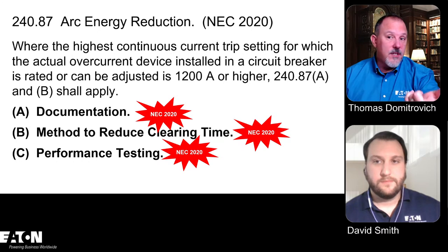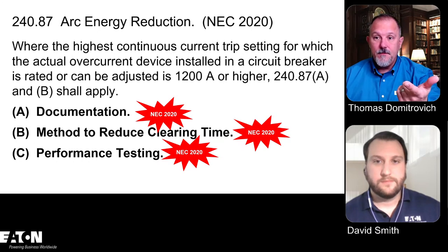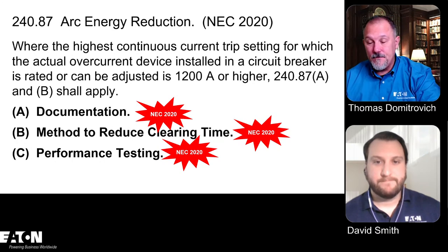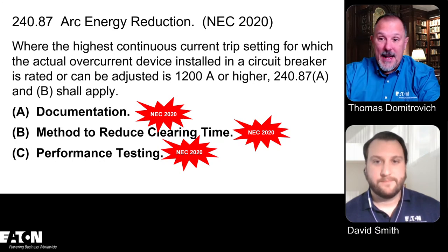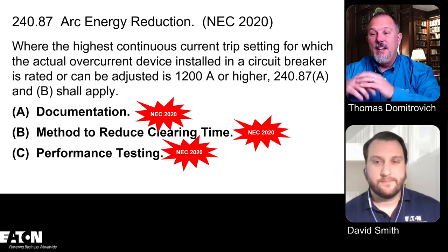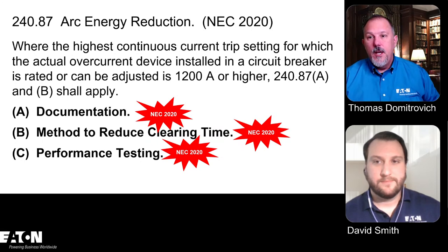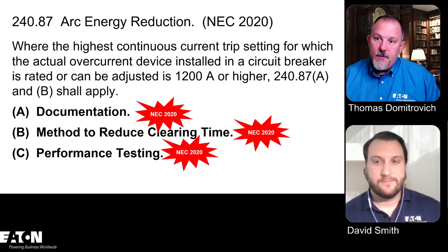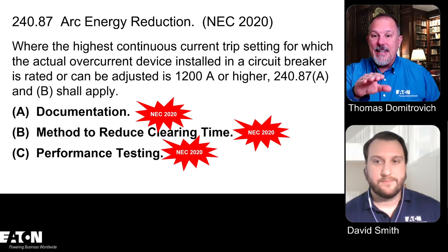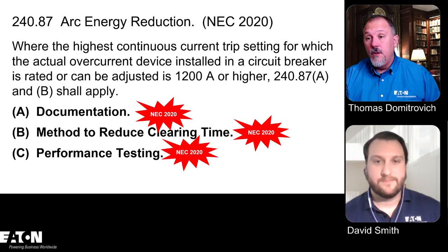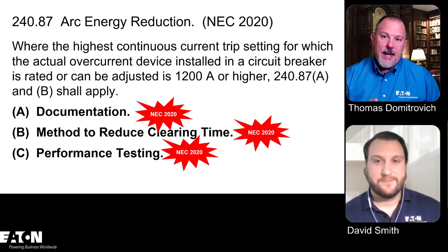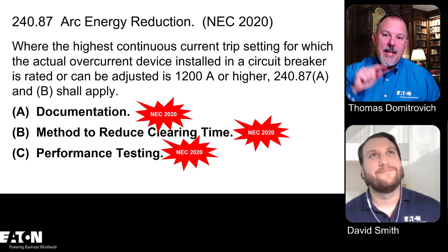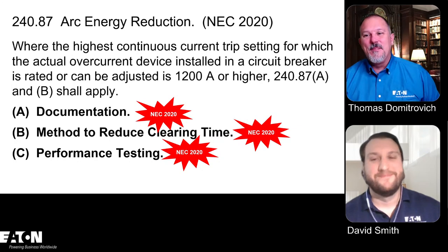Now, you'll notice, David, that we have 240.87 A and B shall apply. Now, we fixed that in the 2023 because that was a public input. What we forgot to do in the 2020 cycle, when we added C, C was new for the 2020 cycle. We forgot to change the parent text to say A, B, and C shall apply.